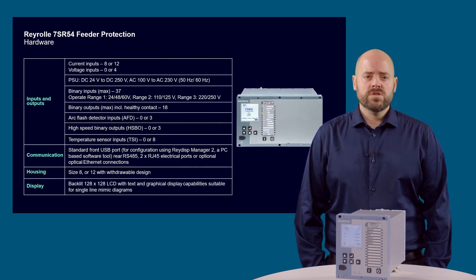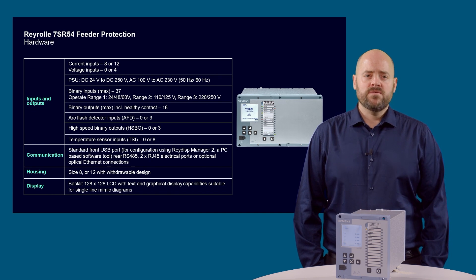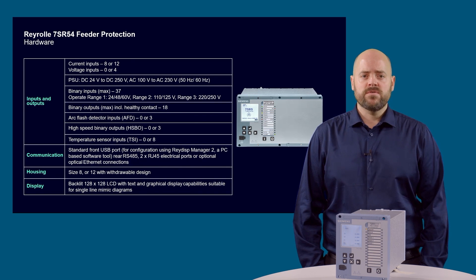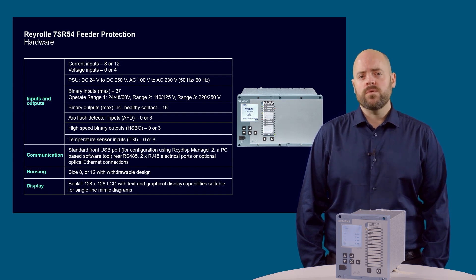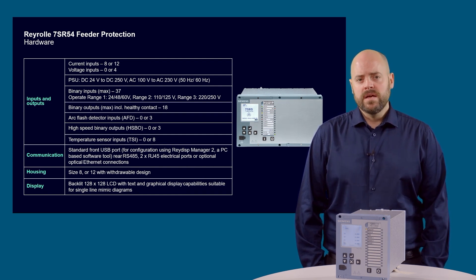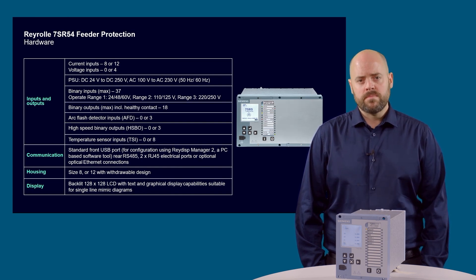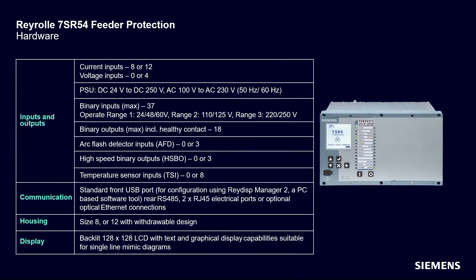Now let's take a closer look at the hardware. 7SR542 two-winding devices have 8 CT inputs and 7SR543 three-winding devices have 12 CT inputs, and both have up to 4 VT inputs. A single power supply covering all substation auxiliary voltage supply levels is used — no separate ordering options are necessary. The binary inputs have selectable operating levels and each binary input can be configured individually if required. There are optional arc flash detector inputs, high-speed binary outputs, and temperature sensor inputs.